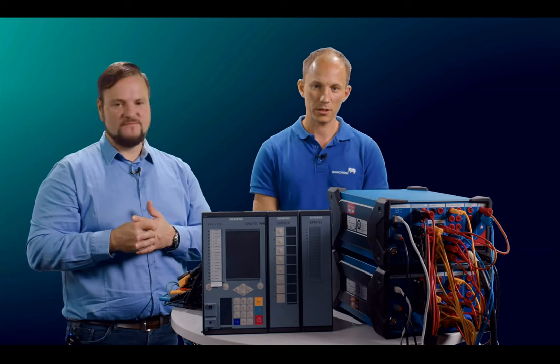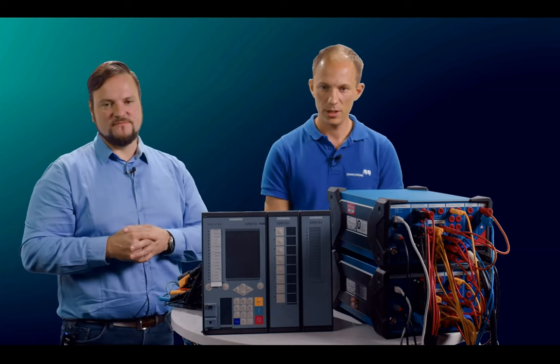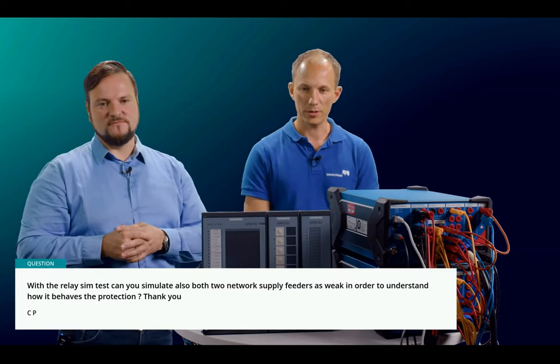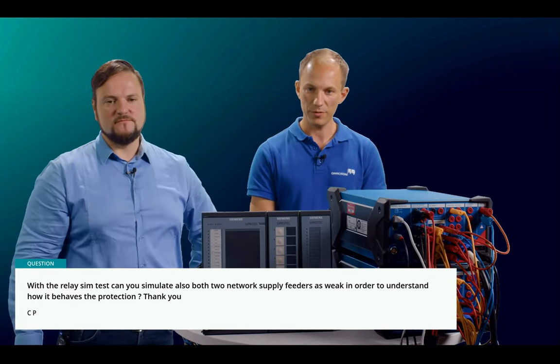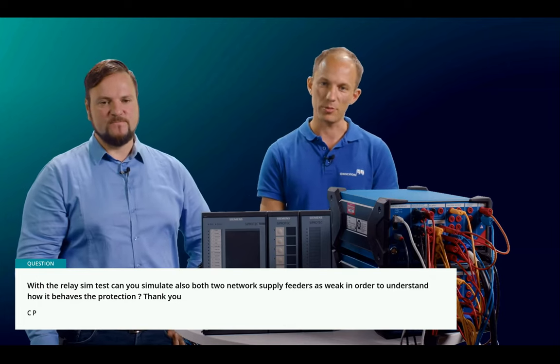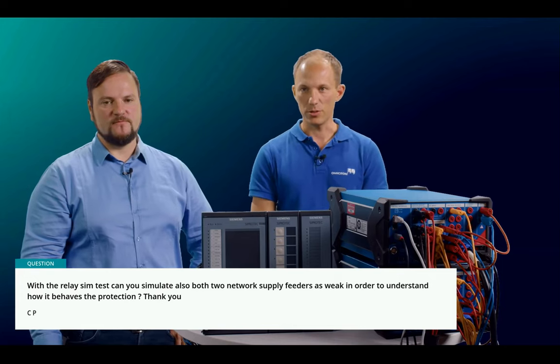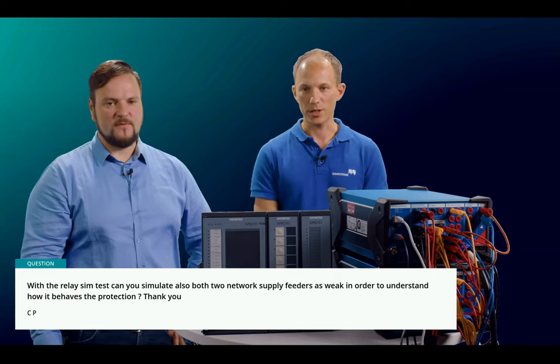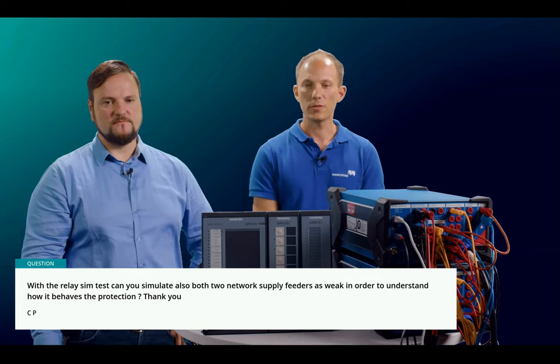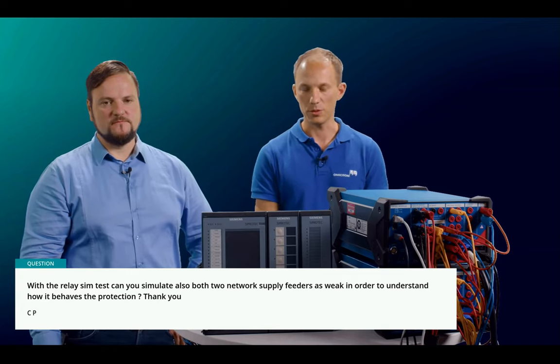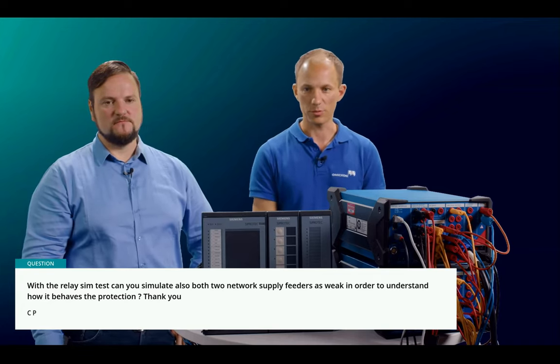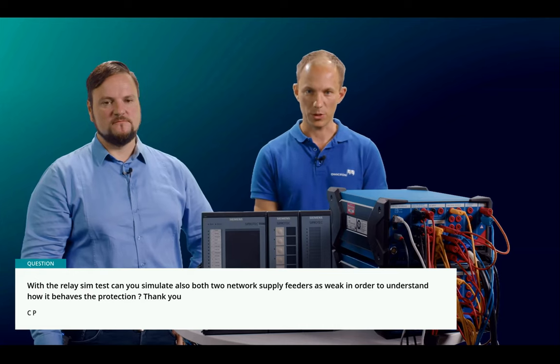Okay, there is another question regarding RelaySimTest. With RelaySimTest, can you also simulate both network supply feeders as weak, in order to understand how the protection behaves? Yes, that's possible. You can adapt the percentage of both infeeds from 0 up to 300%. That's possible.